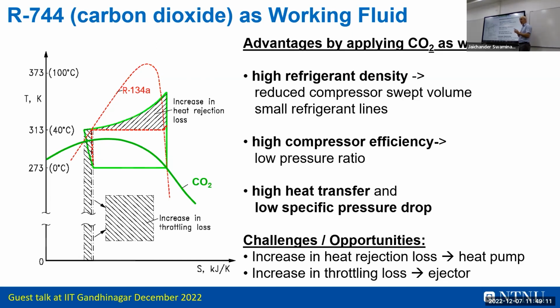It's very important to understand you need to have a high temperature lift on the water side. A low inlet temperature is crucial to utilize it and to cool down the fluid before you do the expansion. If you still have relatively high temperature, you should utilize this expansion work, for example in an ejector - I'll come back to that. We can use this work for something in the system to increase the COP, with a simple device, not too complicated. Expanders are too complicated and the failure rate is high, so it can work for megawatt systems where you have huge ones, but for small units it's too complicated.